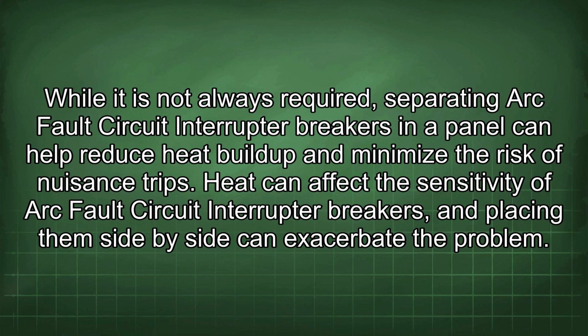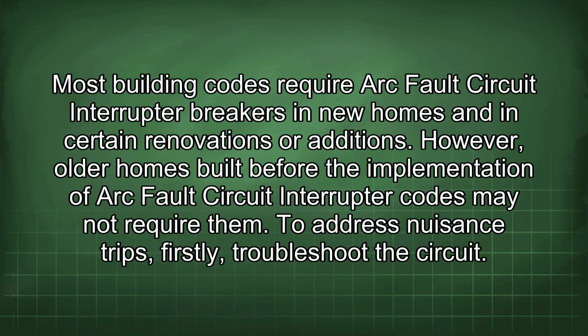Heat can affect the sensitivity of arc fault circuit interrupter breakers, and placing them side by side can exacerbate the problem. Most building codes require arc fault circuit interrupter breakers in new homes and in certain renovations or additions. However, older homes built before the implementation of arc fault circuit interrupter codes may not require them.